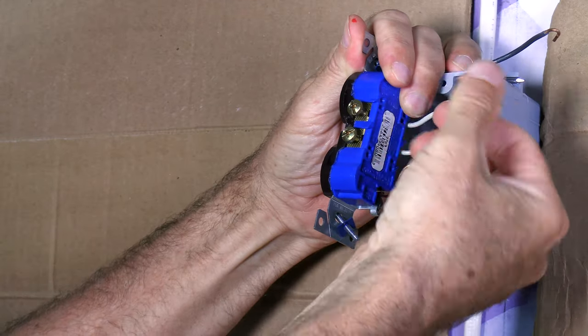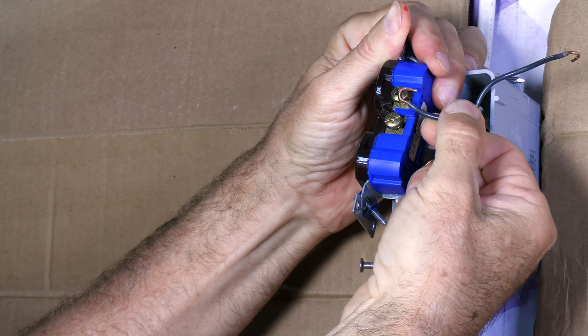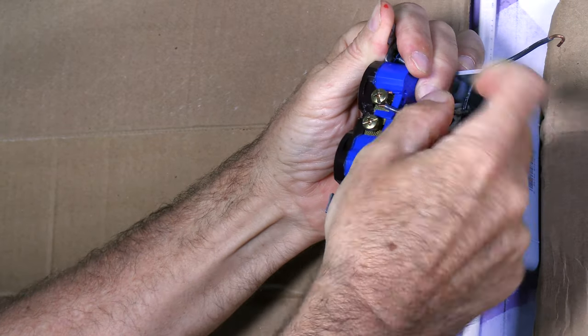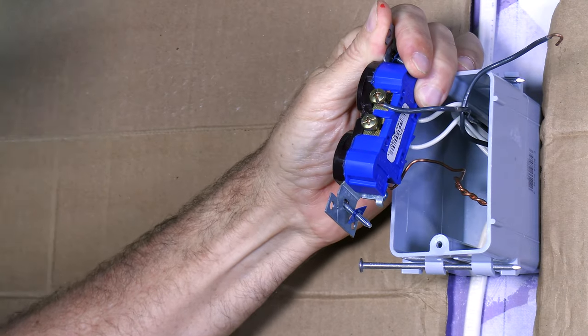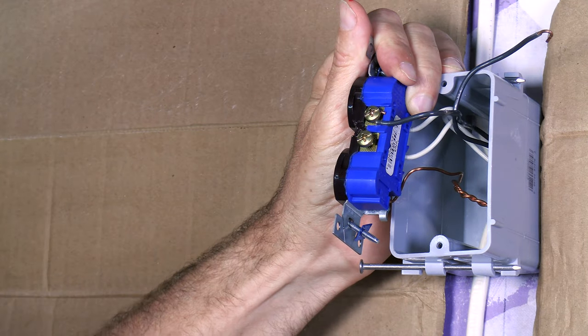Now, when you're putting these loops around this wire, put it on this way right here where the loop is going in the same direction as the screw. Okay. That way, when you tighten it up, it doesn't expand that loop and go away from the screw.